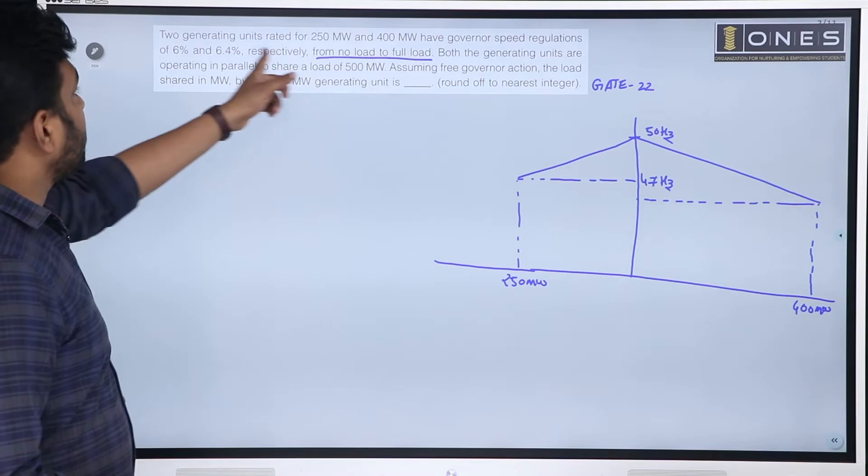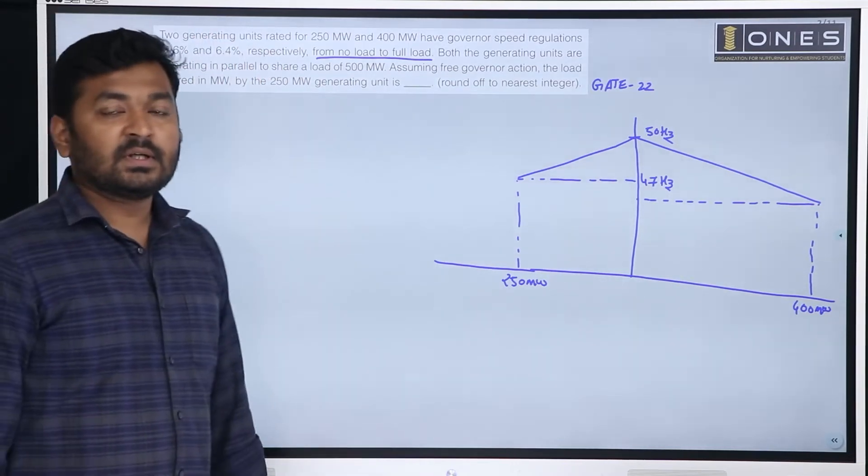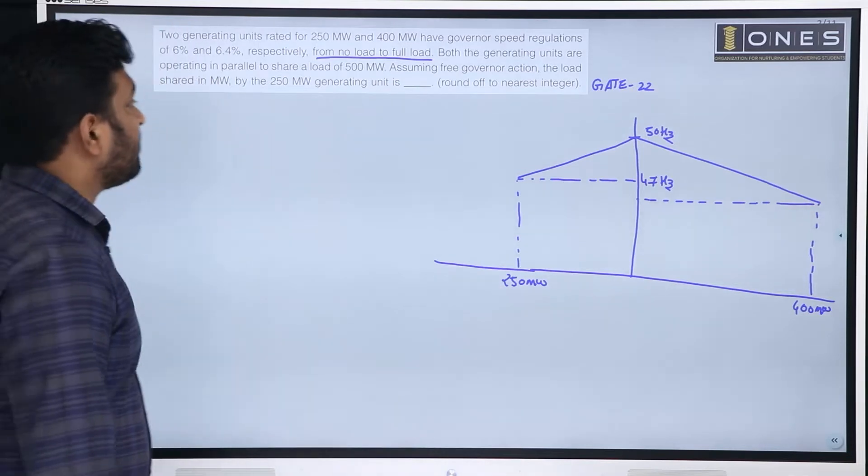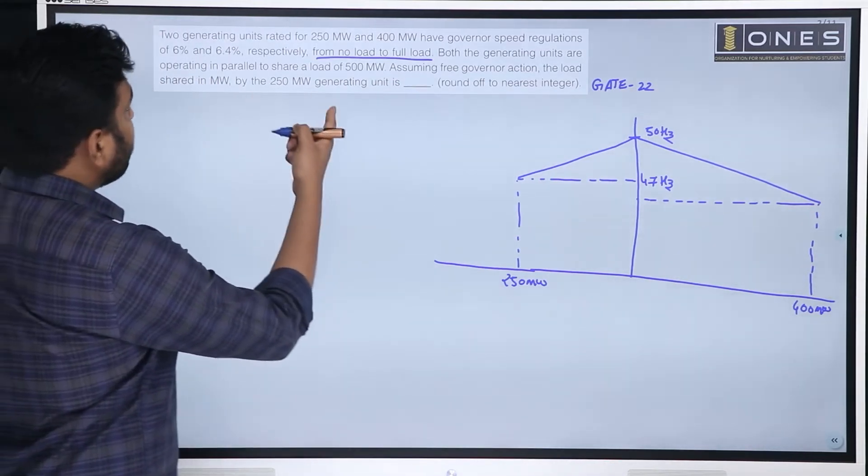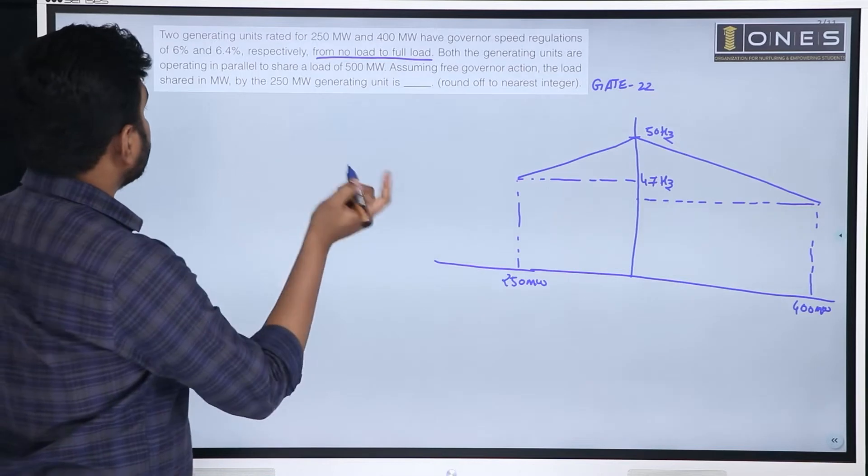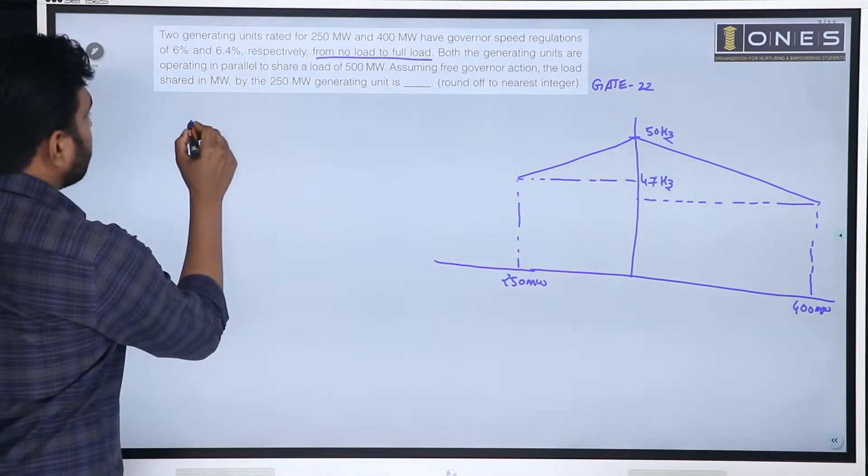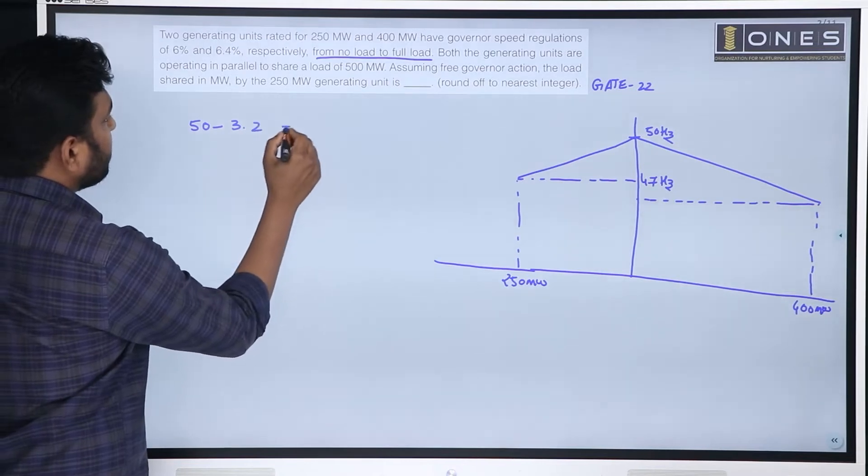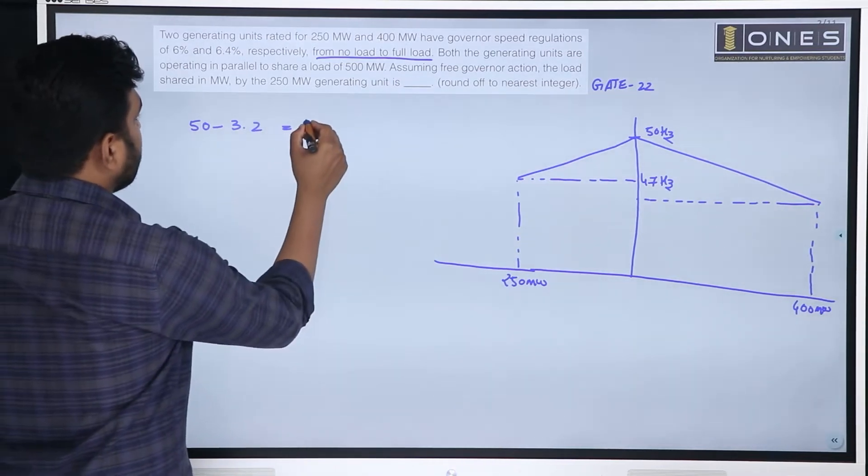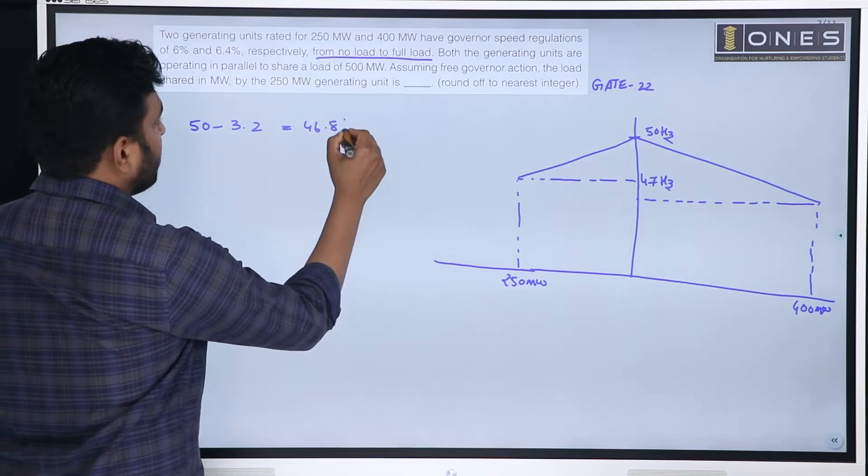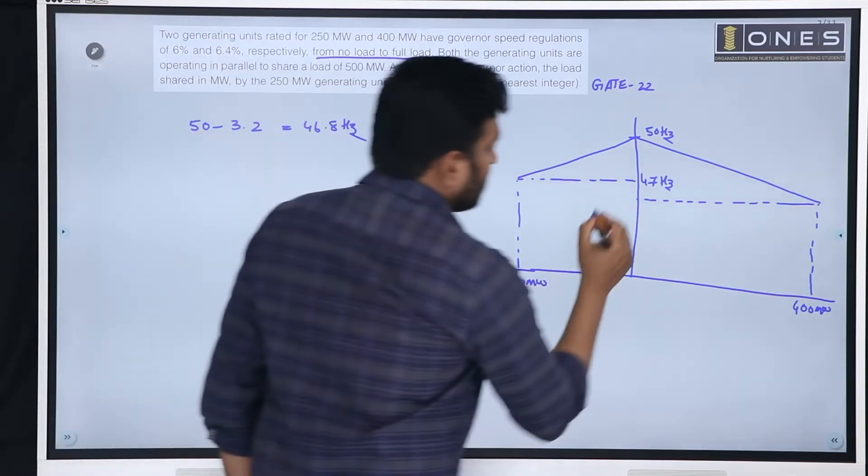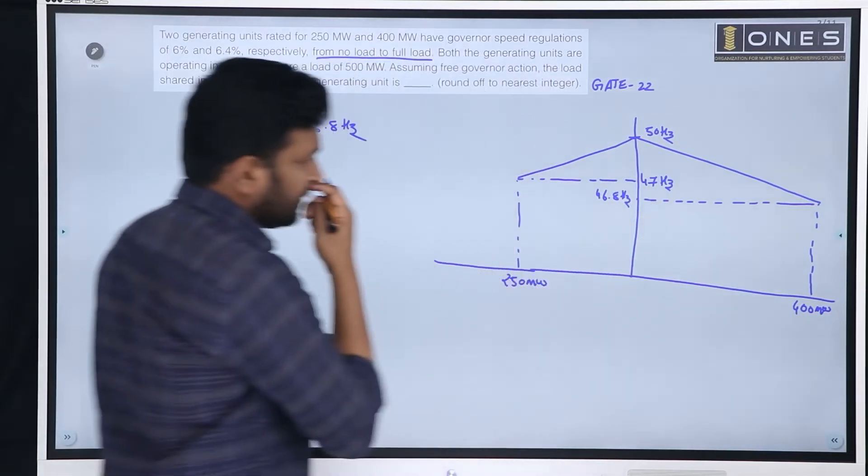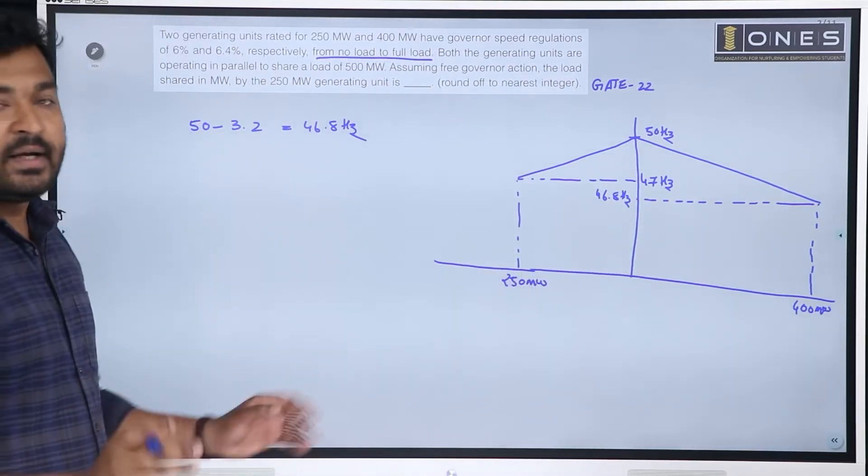400 megawatt, it is 6.4 percent. 6.4 percent at full load frequency, full load frequency will be 50 minus 3.2. It will come as 46.8 hertz. So, this is given data.